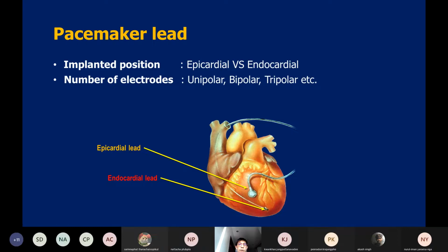And there is a number of electrodes on the leads. The types are unipolar, bipolar, and tripolar. Unipolar is when you have only one electrode on the lead. Bipolar is when you have two electrodes, one on the tip of the lead and one on the lead itself. And tripolar, we don't usually use it often at present. We also have to consider the implant chamber. The leads for the atrium and the leads for the ventricle have different types and different anatomy.